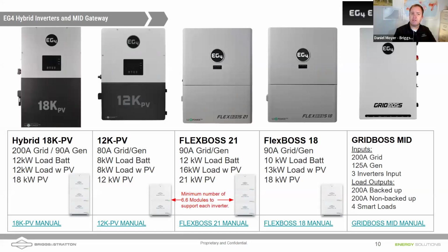18K PV can do 12,000 watts from batteries to load. It can surge, of course. 12K PV can do 8,000, and then the 21 can do 12,000 from batteries to loads, 10,000 for the 18K. And you can see the nomenclature that EG4 has used for the 18, 12. That's representative of how much DC coupled solar we can bring on these systems.